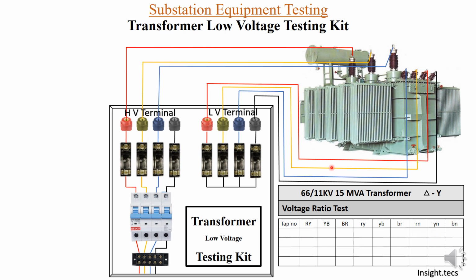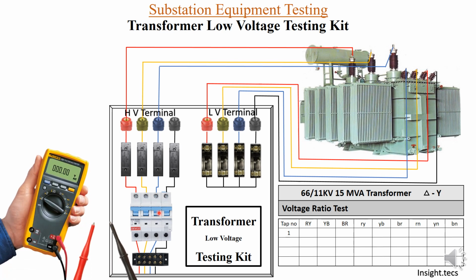Assuming that the transformer is at tap number 1 right now, we will see how we can measure the voltage. First of all you will have to provide all the fuses on the HV side. We will next turn on the MCB. Once the MCB is turned on, we will require a multimeter. So we have a multimeter over here to measure the voltage between the terminals of HV and LV. Now let us begin to measure the voltage.